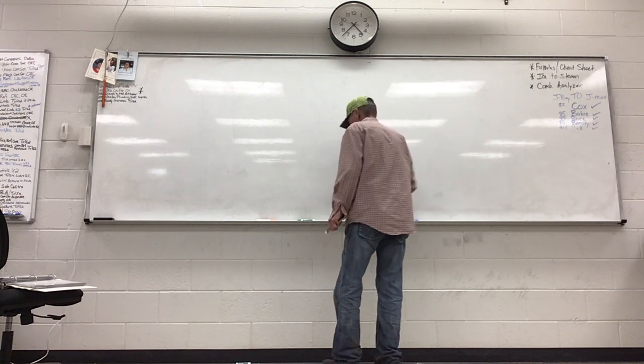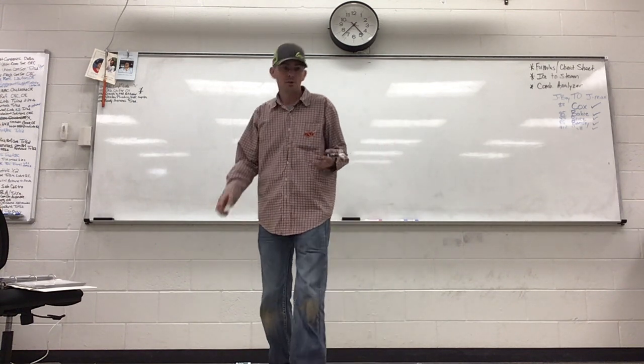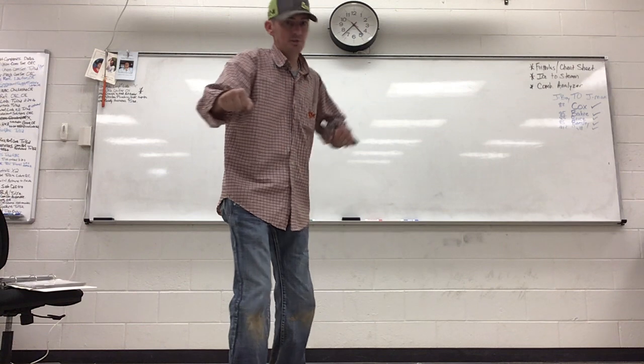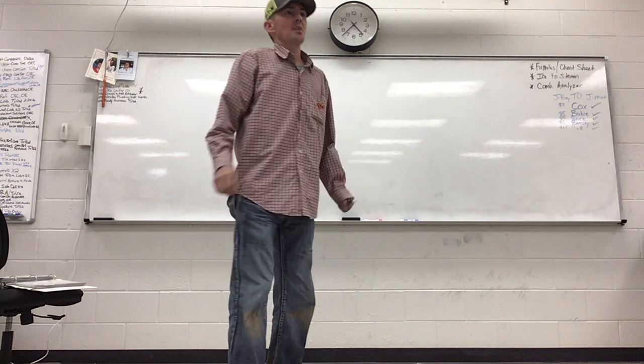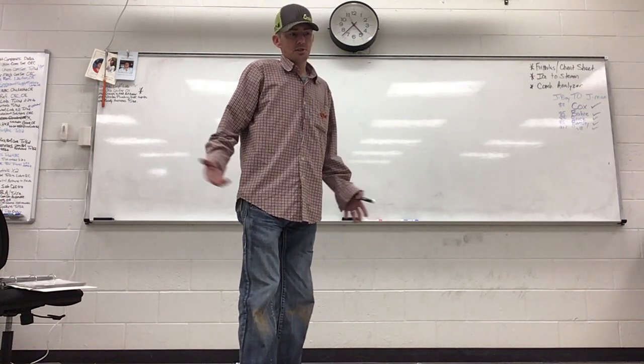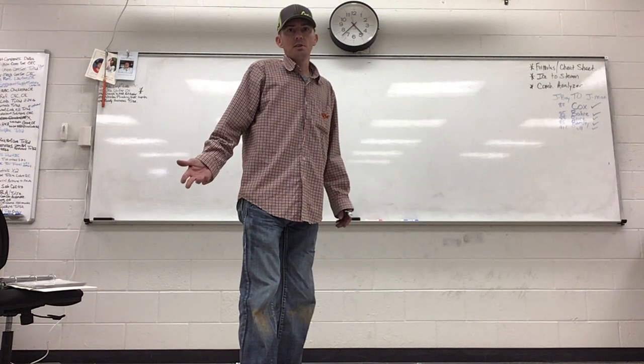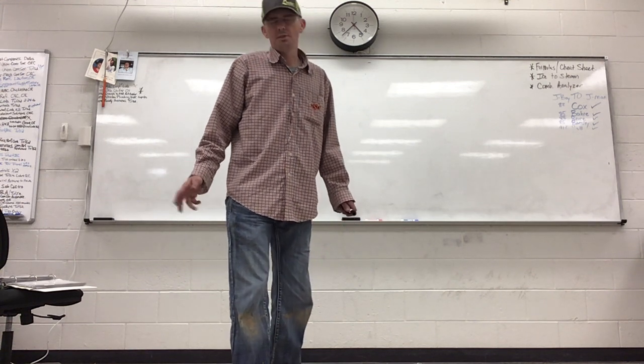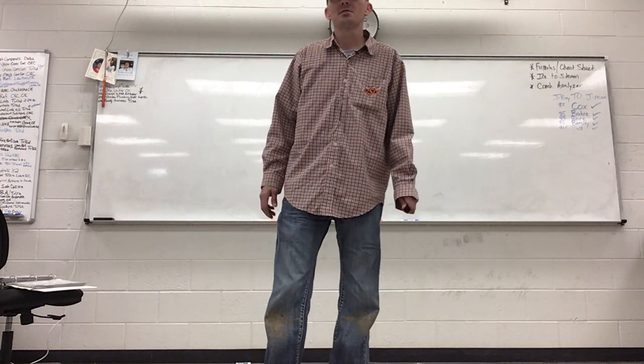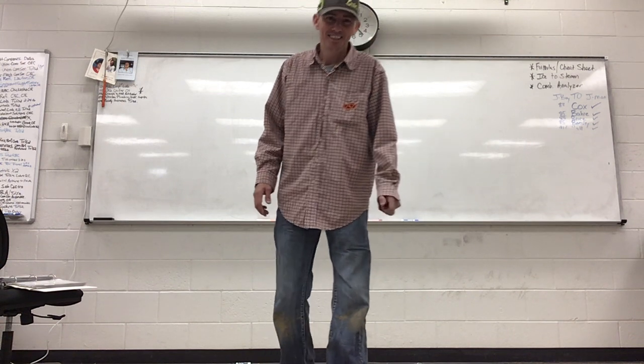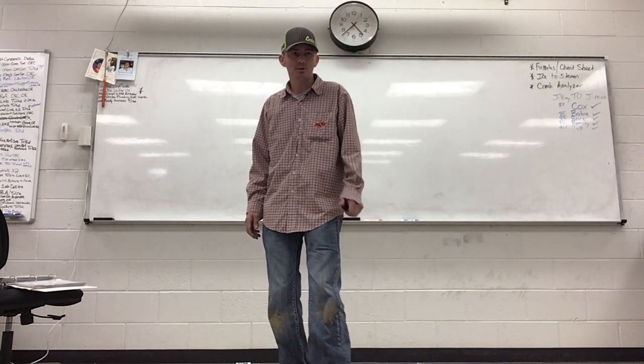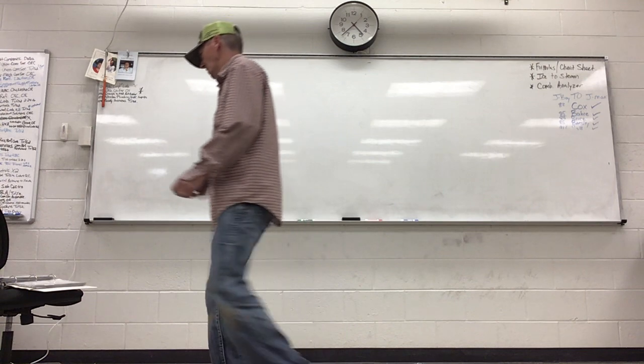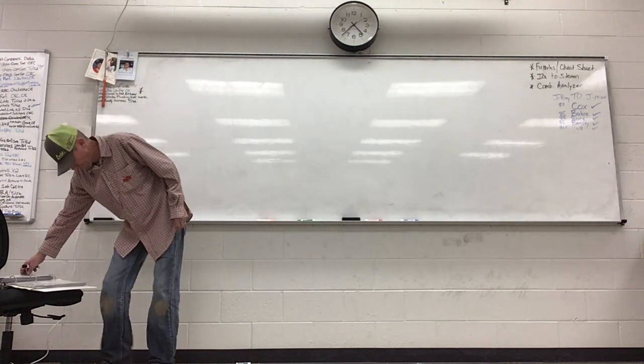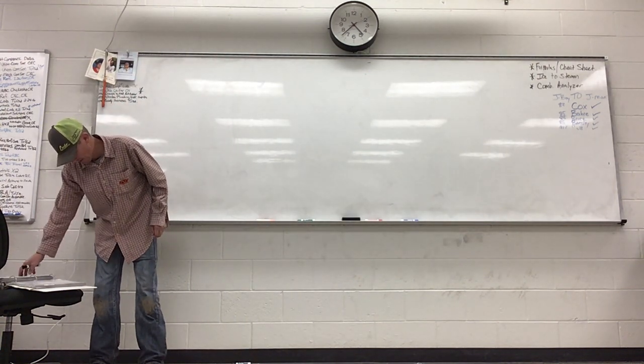We're going to soft start it as a Y, and then transition to a delta after it gets up to speed, just to limit the inrush current. That's the name of the game on soft start stuff: limit the inrush current. We want to limit that peak, right? All right, let's see what else I got next.